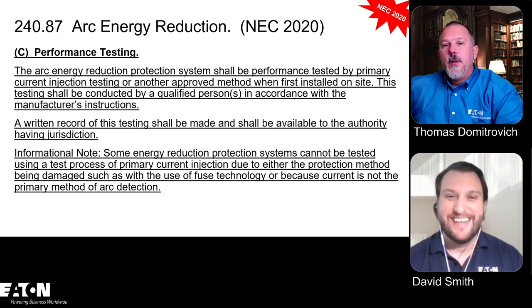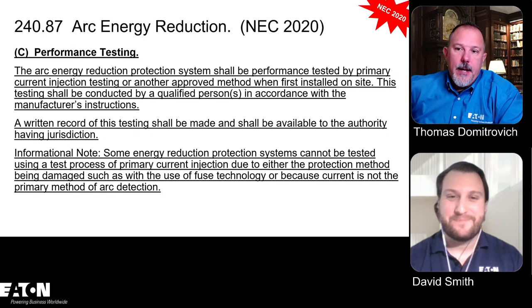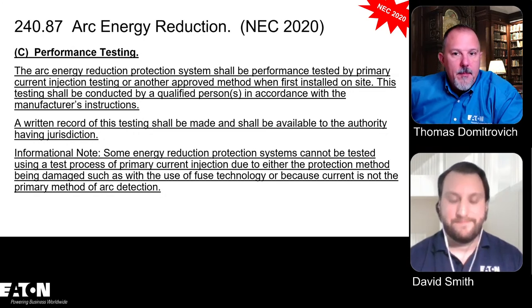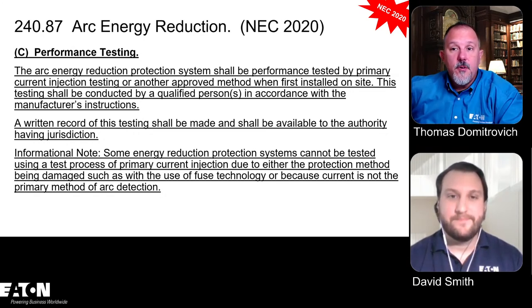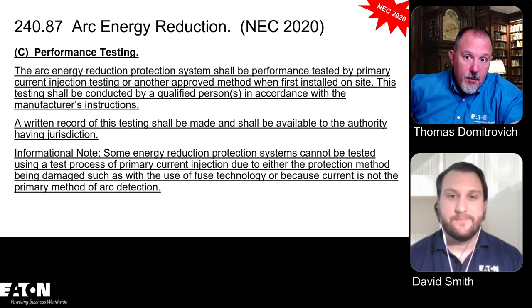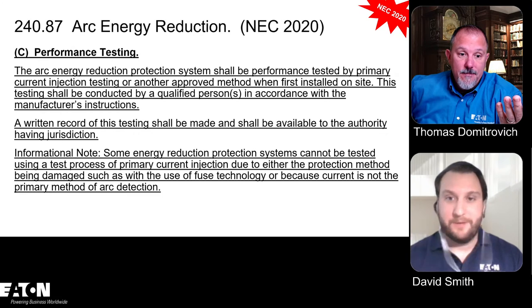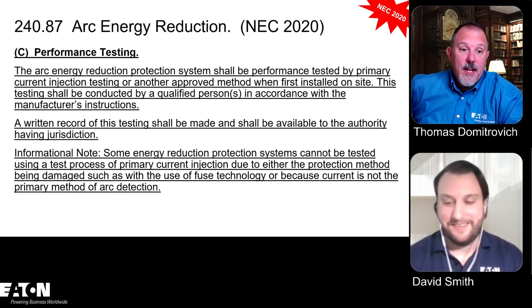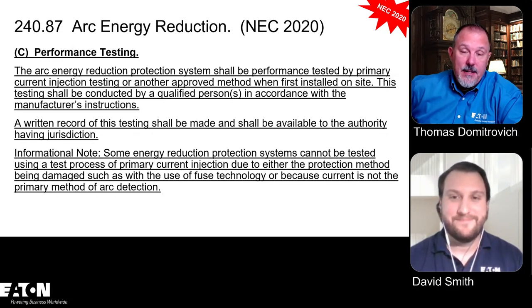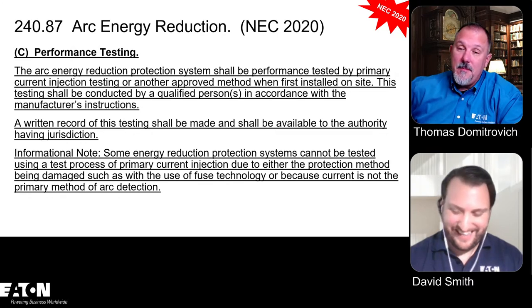But that's the language that's in C. It has to be performance tested by primary current injection testing or another approved method. And why did we have to put the other approved method in, David? Because of fuses. You could damage it, right? Like a fuse. Don't want to do that. If you have a fuse, we always say test every fuse when you first put it in. But, you know, we'd make a lot of money on fuses.